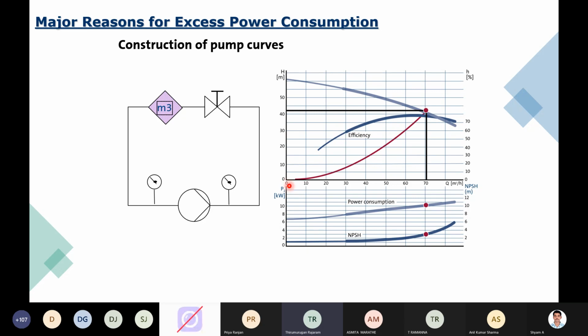So from the flow condition, maybe from 10 meter cube, it can go up to 80 meter cube. So this is your boundary limit for this particular product. Now within this flow and head boundary limit, your power consumption will keep on increasing whenever you increase your flow. And same thing, your NPSH keeps on increasing.